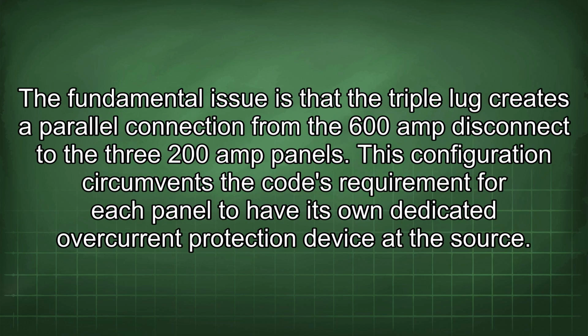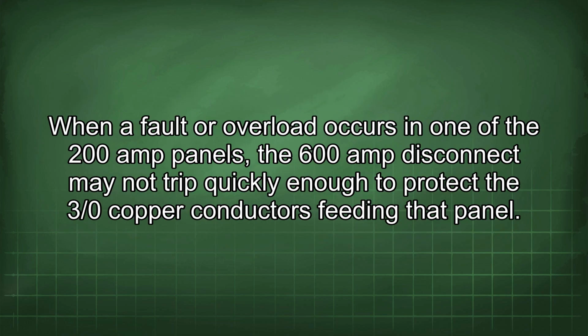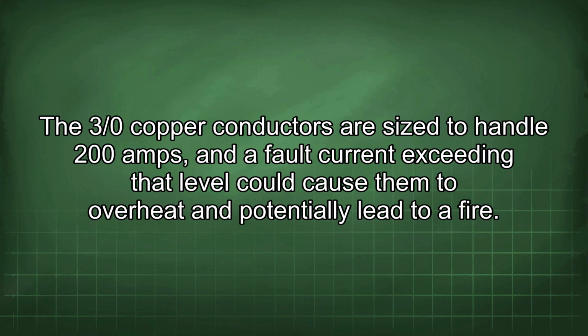The fundamental issue is that the triple lug creates a parallel connection from the 600 amp disconnect to the 3 200 amp panels. This configuration circumvents the code's requirement for each panel to have its own dedicated overcurrent protection device at the source. When a fault or overload occurs in one of the 200 amp panels, the 600 amp disconnect may not trip quickly enough to protect the 3/0 copper conductors feeding that panel. The 3/0 copper conductors are sized to handle 200 amps, and a fault current exceeding that level could cause them to overheat and potentially lead to a fire.